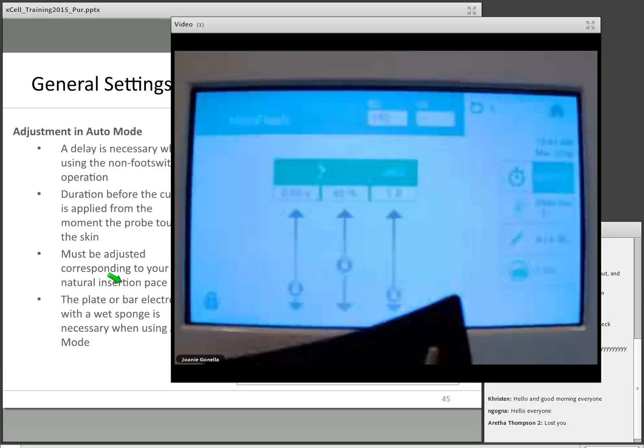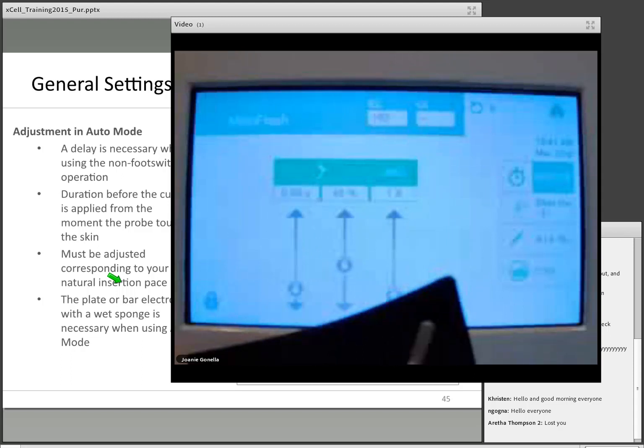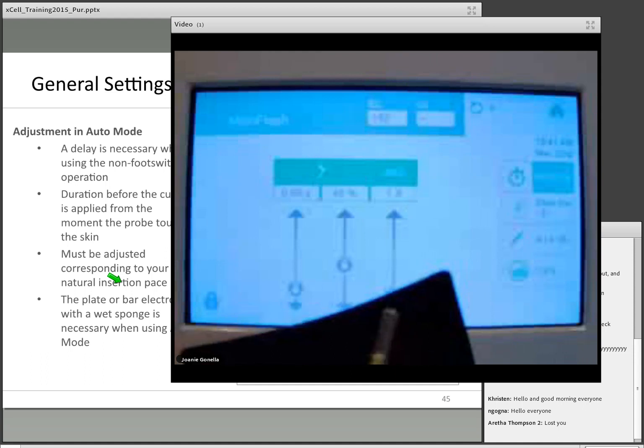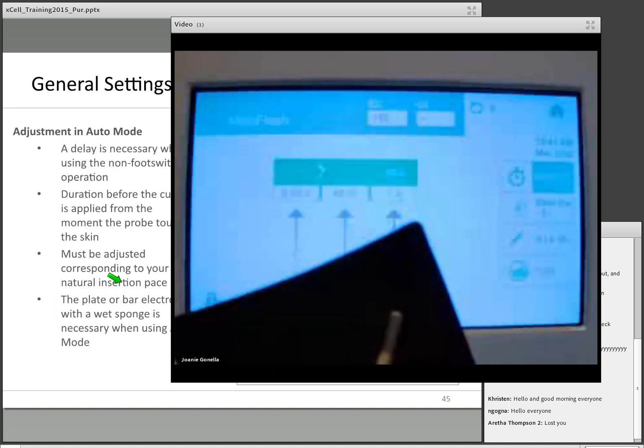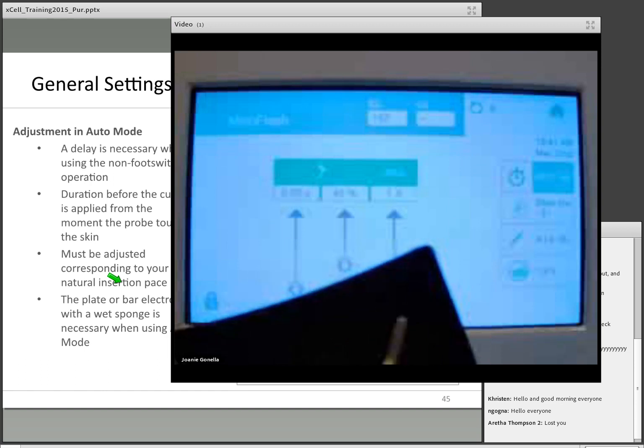The first noise means it sensed moisture. When I lift out of the skin, let's say my insertion is incorrect and I pull out of the skin, that's when it makes that tunk noise. That tells me it's interrupted the current, essentially canceled it. It's not going to deliver the pulse until you stay the appropriate amount of time.